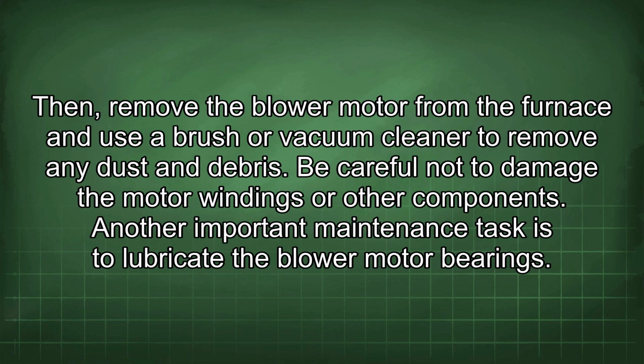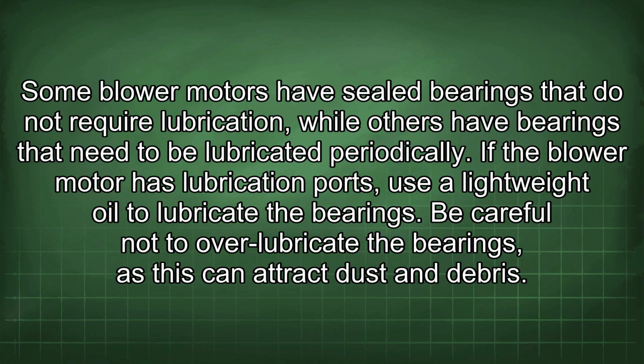Another important maintenance task is to lubricate the blower motor bearings. Some blower motors have sealed bearings that do not require lubrication, while others have bearings that need to be lubricated periodically. If the blower motor has lubrication ports, use a lightweight oil to lubricate the bearings. Be careful not to over-lubricate the bearings, as this can attract dust and debris.